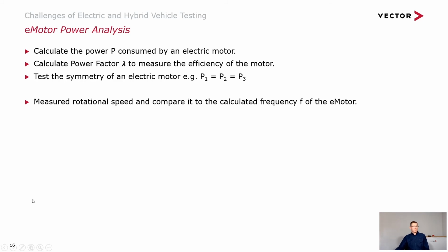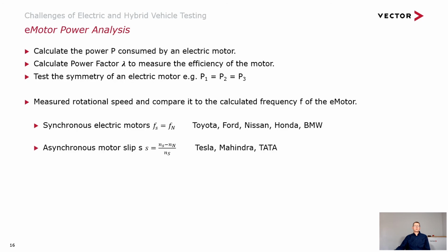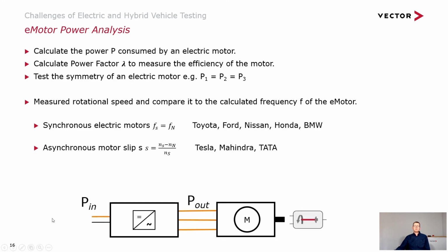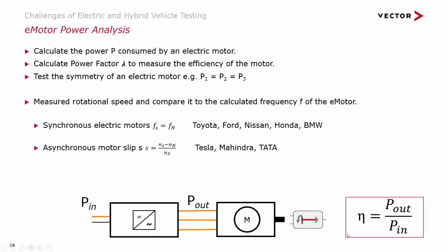If we use a shaft encoder, then we can use that to compare the rotational speed of the motor with the frequency of drive of the motor. And we've got two types of motor, synchronous and asynchronous, used by different companies, and we can work out the symmetry and also the slip of those motors with the right analysis software. So here's power into the inverter, into the motor, and a shaft encoder. And we can work out the efficiency of that system.